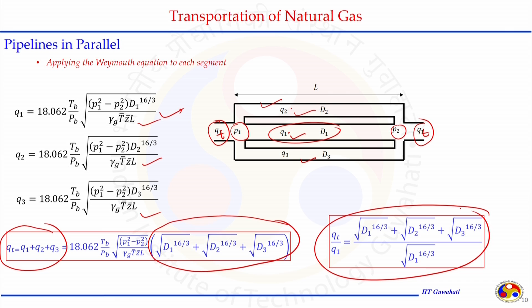If we sum up, we get QT is equal to Q1 plus Q2 plus Q3, and after doing the summation, we see the L is common in all three expressions. It is just the diameter that is different. So, we are going to get the diameter in this form getting summed up, because the different diameter pipelines are in parallel. The total Q should depend on the diameter of the pipeline installed parallel to the existing one. Similarly, we can calculate how much increment happens in terms of the gas capacity. We can divide this QT considering just Q1 is there. So, that we already have this expression. If we do so, we get this expression, and in this expression we see even the length is cancelled out, because all the three lines are occupying the entire length L of the existing pipeline, and it is just a matter of what size of diameter pipeline is installed in parallel to the existing one. That is going to calculate the increase that is going to be in the Q value.